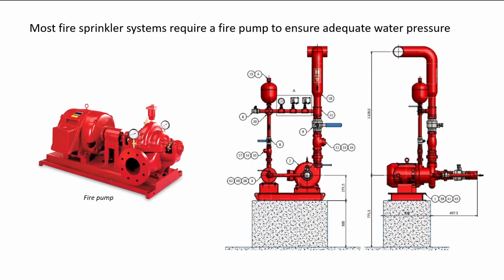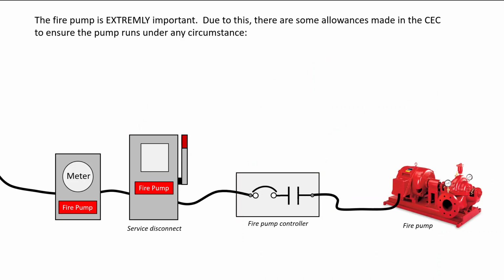Many fire sprinkler systems require a fire pump to ensure adequate water pressure. This is often seen in systems that have multiple stories of building, like 10 stories high. How do you get the water up there? Well, you need a fire pump. And a fire pump consists of an electric motor and a water pump. The fire pump is extremely important. Due to this, there are many allowances made in the CEC to ensure the pump runs under any circumstance.